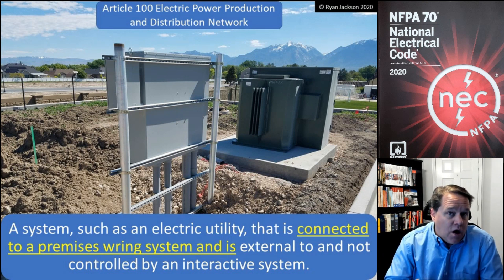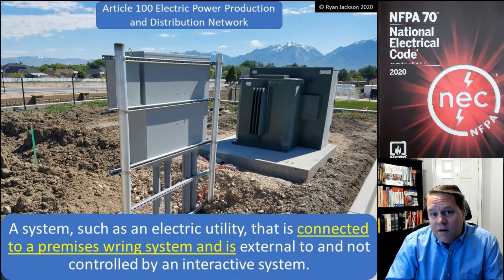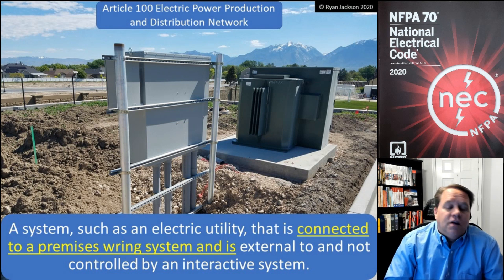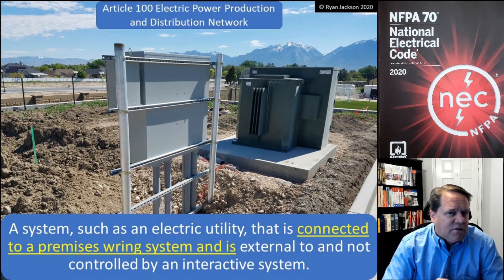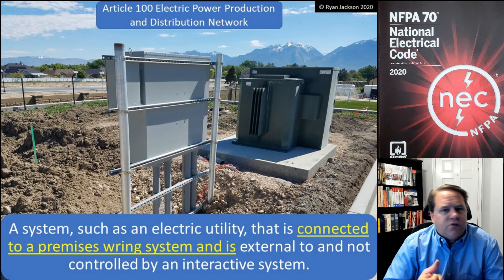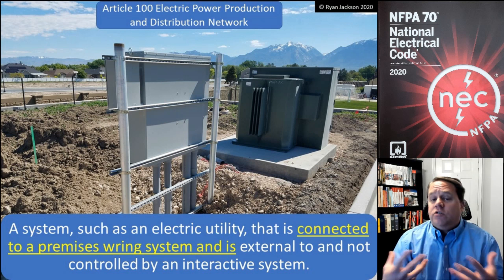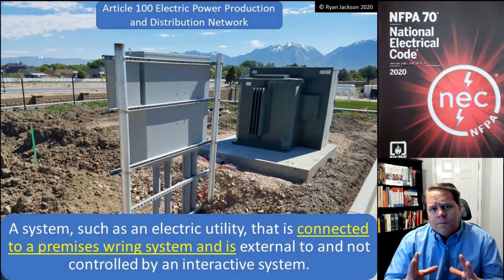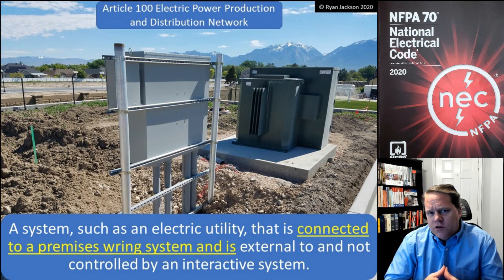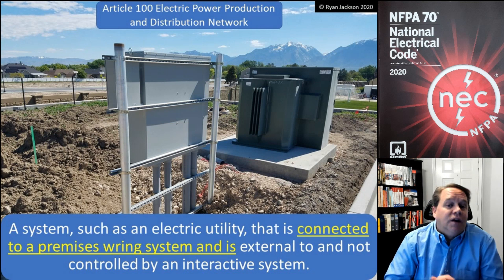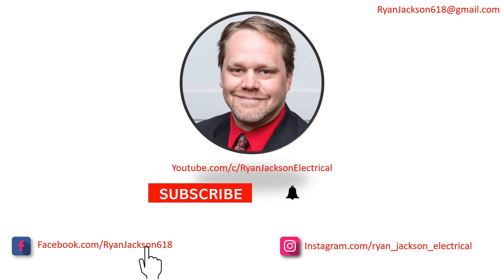I think this is a term you're going to see take off, and it might ultimately take the place of the term utility. When you go to 90.2(B), it says that utilities have exemptions for certain types of installations — service drops, service laterals, associated metering, and installations on utility-owned easements or public rights-of-way. So you're probably eventually going to not see the word utility in 90.2(B) — you might end up seeing the term electric power production and distribution network instead.